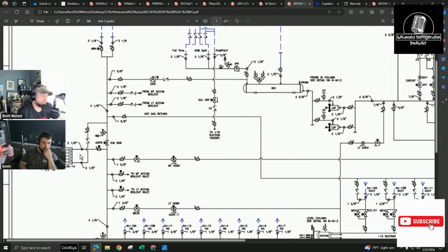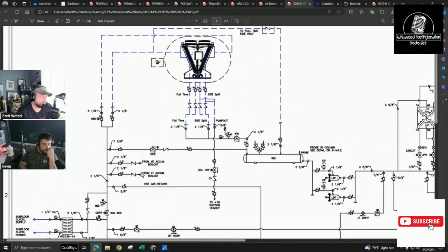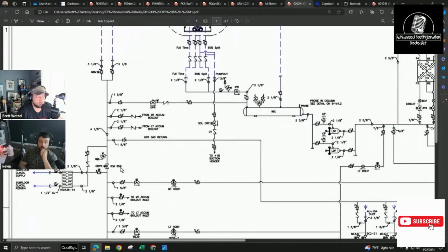Oh, look, and they're also using the discharge gas here for the subfloor heat exchanger. So they're running the glycol through here. Yep. Just to keep the floor from heaving. Which you could probably do on a facility that big. You could probably get a lot of de-superheating off that.